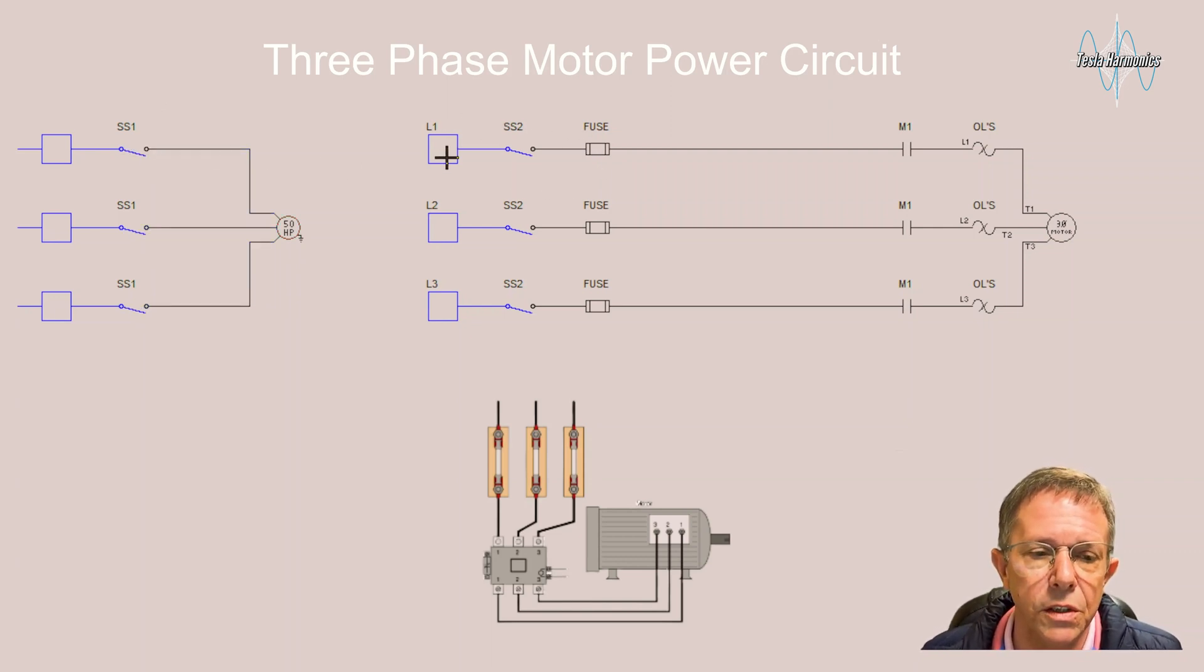I've taken the disconnect with the fuses, so I got startup and running protection for the motor. And instead of taking the power directly to the three-phase motor, I've taken it across three open contacts that are in this motor starter.